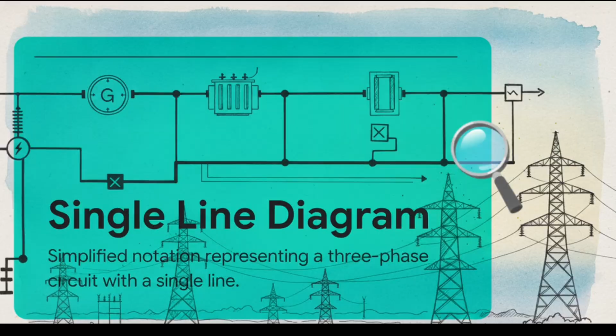But an SLD is way more than just a pretty map. Without this elegant single-line simplification, engineers couldn't perform the critical mathematical analyses required to keep the grid balanced. SLDs are the foundation for conducting load flow studies, executing short-circuit analysis, and coordinating protective relays, which ensures that a single fault in one neighborhood doesn't suddenly black out your entire city.